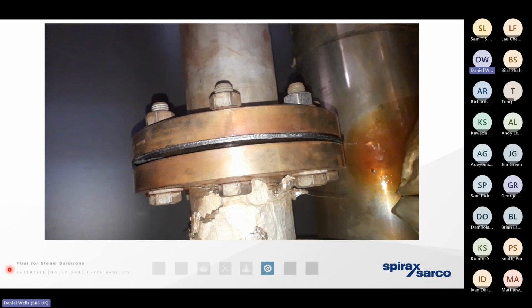Because if we're moving steam at 40 meters per second, that buildup of pressure that's causing that water hammer is forcing the condensate across the flanges and the gaskets at such a pressure that it's causing the flanges themselves to erode, which is resulting in that passing condensate and that water hammer effect. So it would be advised to take a broader look at the overall infrastructure and find the root cause of the problem. And it could be down to a number of things.